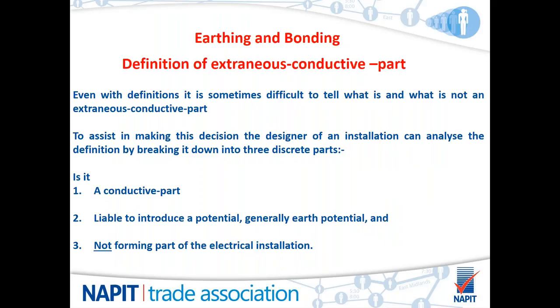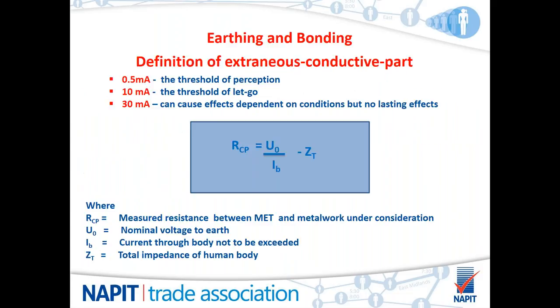Okay, so a definition of extraneous conductive part. Even with the definitions, it can be difficult to tell what is and what isn't an extraneous conductive part. A way to assist in making this decision, the designer of an installation can analyse the definition by breaking it down into three discrete parts. Is it one, a conductive part, two, liable to introduce a potential, generally earth potential, and three, is it not forming part of the electrical installation?